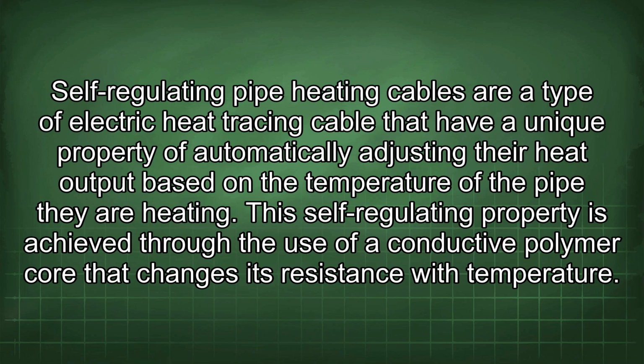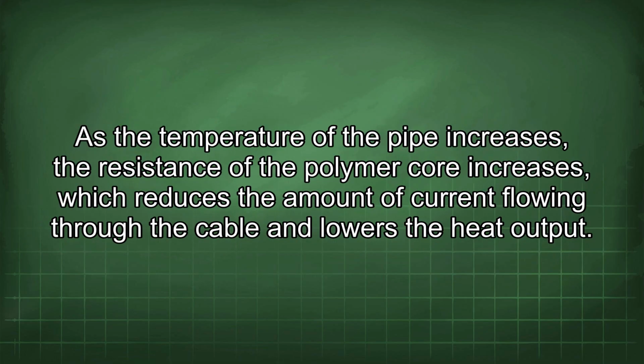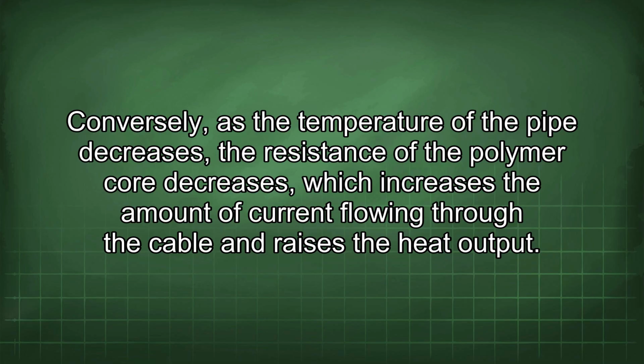Self-regulating pipe heating cables are a type of electric heat tracing cable that have a unique property of automatically adjusting their heat output based on the temperature of the pipe they are heating. This self-regulating property is achieved through the use of a conductive polymer core that changes its resistance with temperature. As the temperature of the pipe increases, the resistance of the polymer core increases, which reduces the amount of current flowing through the cable and lowers the heat output. Conversely, as the temperature of the pipe decreases, the resistance of the polymer core decreases, which increases the amount of current flowing through the cable and raises the heat output.